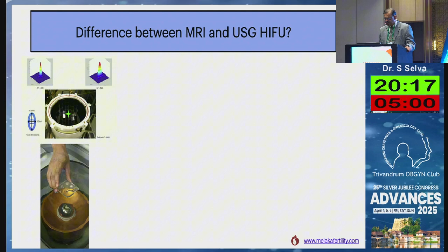So the difference between MRI-based HIFU and ultrasound-based HIFU is in the transducer. In the MRI-based HIFU, the transducer movement is limited by the size and the hole in the gantry of the MRI, and in the ultrasound-based HIFU, the movement is not limited. Actually, this transducer, which is the ultrasound-based HIFU, can move 12 centimeters up, down, and sideways. And this is a big advantage because the MRI-based HIFU uses something called a phase array transducer. And this phase array transducer has 256 small focuses, and this focus actually moves.